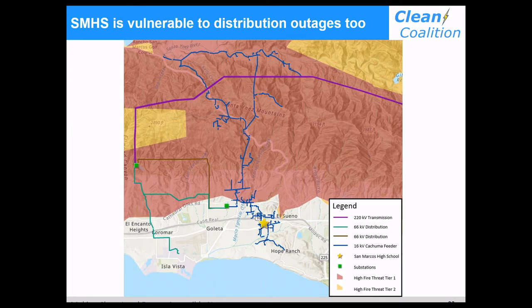In addition to San Marcos being very vulnerable to the transmission system, shown here as this purple trace, it's also very vulnerable to the distribution system. San Marcos is the little star here, a bit hard to see. The transmission line terminates into the Goleta substation, the namesake for the Goleta Load Pocket. It takes 220 kV transmission in and has 66 kilovolt distribution feeders coming out.